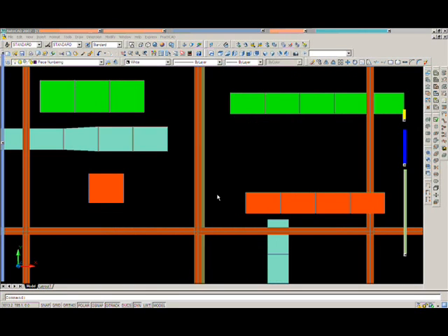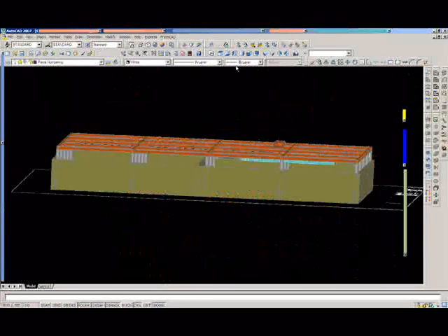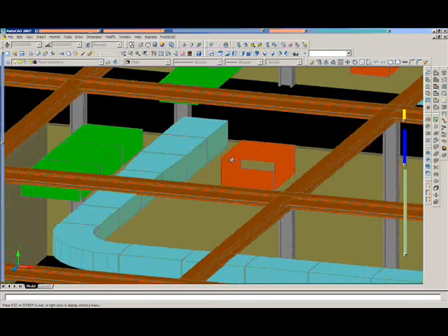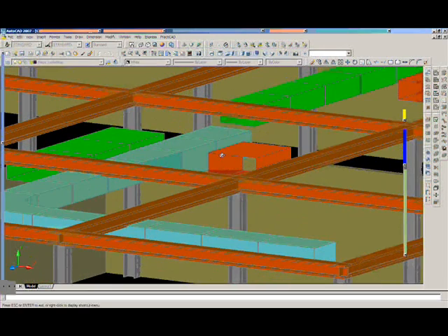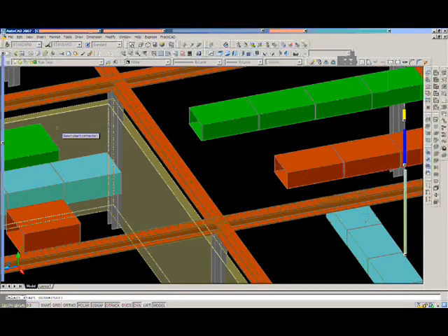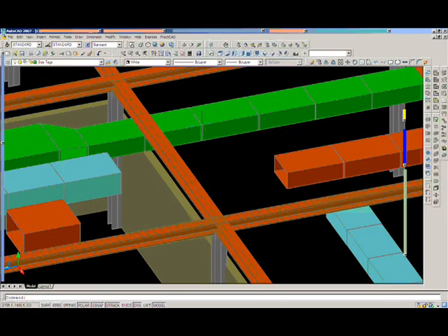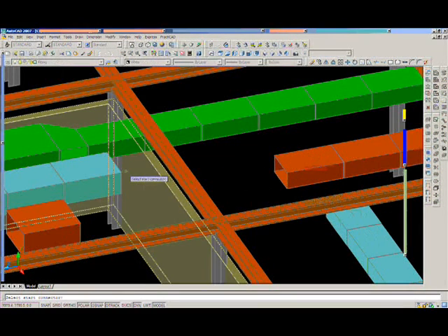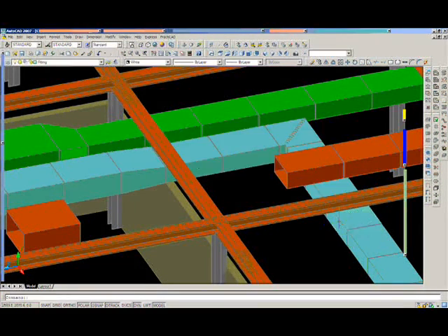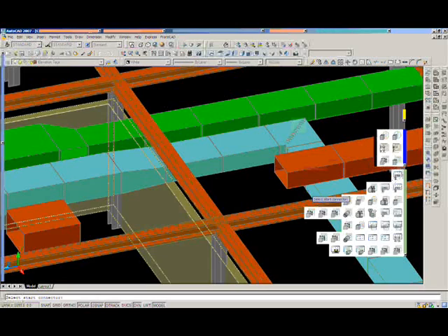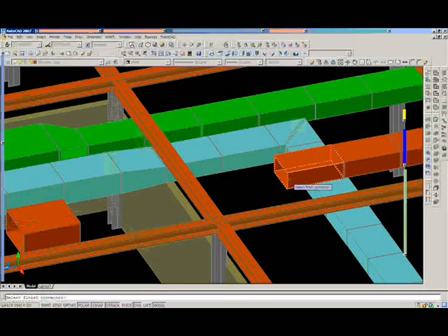Just like we do for full duct lines, we can detail or route duct in between breaks and duct lines. This makes it easy to fill duct between two points, even if they are on different planes. You can see here as we put our drawing on the side view, and then as we orbit it, that we have duct with different sizes that are at different heights. Watch as we use our routing feature to route in between these three duct lines. The fittings that we are using are selected by the user. For example, we are going to connect this piece of duct in blue to the other duct line. You will notice that it decides to use rectangular duct followed by a square elbow with turning vanes in it. That was user defined. He specified it during the automatic.